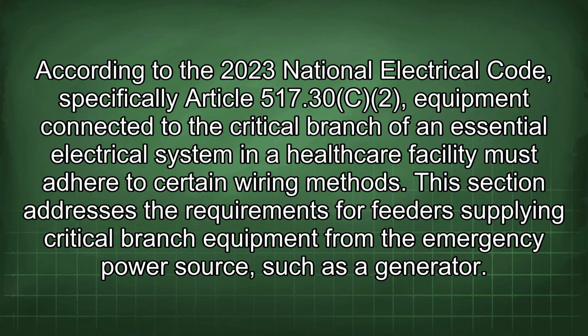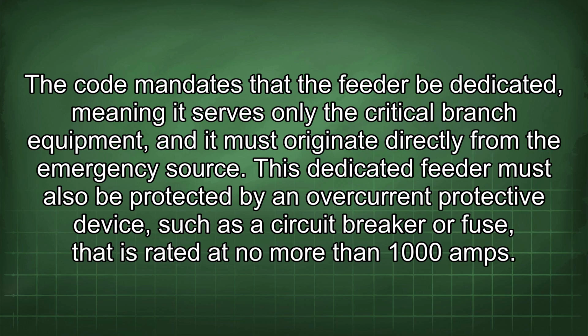According to the 2023 National Electrical Code, specifically Article 517.30(C)(2), equipment connected to the critical branch of an essential electrical system in a healthcare facility must adhere to certain wiring methods. This section addresses the requirements for feeders supplying critical branch equipment from the emergency power source, such as a generator. The code mandates that the feeder be dedicated, meaning it serves only the critical branch equipment, and it must originate directly from the emergency source.